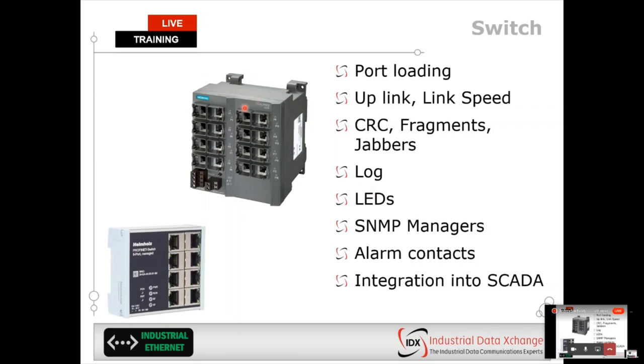These switches will often have integrated SNMP managers, or support the SNMP function. I'll talk about SNMP in a minute, but it's a diagnostic protocol that can give useful information on the network. It could have alarm contacts, sound a siren, send a digital input to the SCADA system, flash lights if there are errors, and integrate their data directly into a SCADA network.